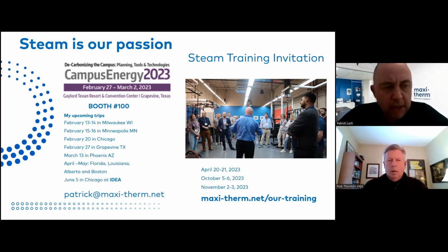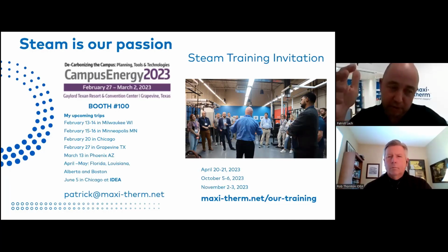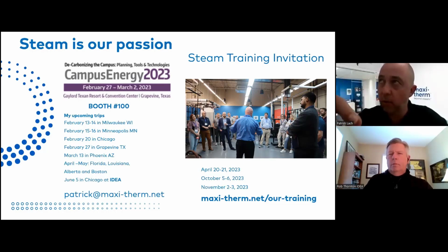Exactly. Pretty much all our purchase orders are placed in Canada, but mainly in the US. So for instance, at the inlet we have a high performance butterfly valve, tight shutoff, class 6. Again, I refer to my video on YouTube, where you'll see I talk about this. And we use Bray valve, which is based in Houston. The main component outside of Canada and the US, though the order is placed in the US but it's manufactured in Germany, is the control valve on the condensate. Since it's the only moving part, we wanted to put something very reliable, and easy to fix and troubleshoot also. So we decided to go with that manufacturer for that moving part.